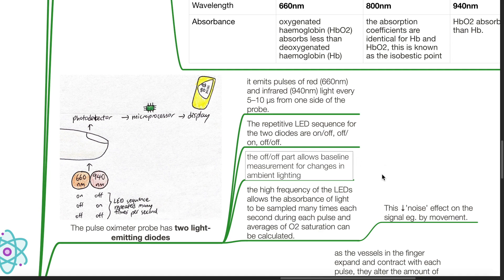The high frequency of the LEDs allows the absorbance of light to be sampled many times each second during each pulse, and averages of oxygen saturation can be calculated. This reduces the noise effect on the signal, for example from physical movement.